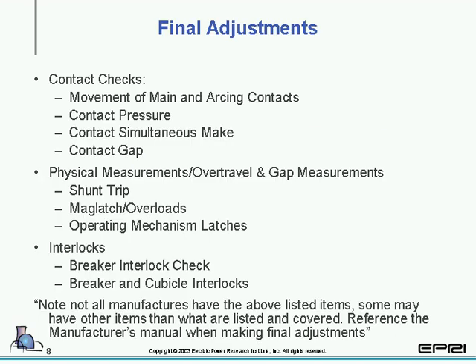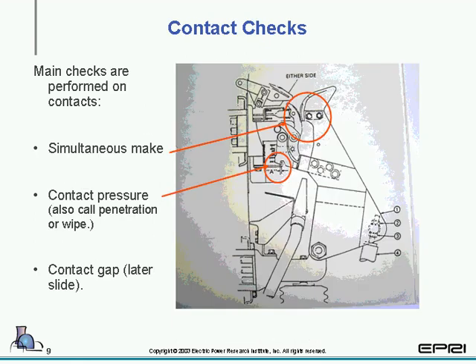That pretty much completes the section of what you want to do with visual. Now we're taking a look at the final adjustment. We're going to be taking a look at the contacts, physical measurement, over travel and gaps, and the interlocks. And we have a little note that not all manufacturers have the above listed items. Some may have other items than what is listed and covered. And of course you want to use the reference manufacturer's manual when making final adjustments.